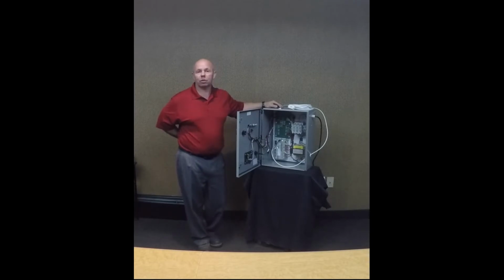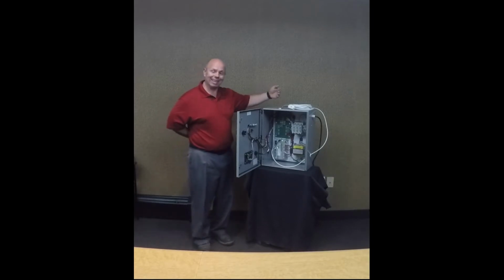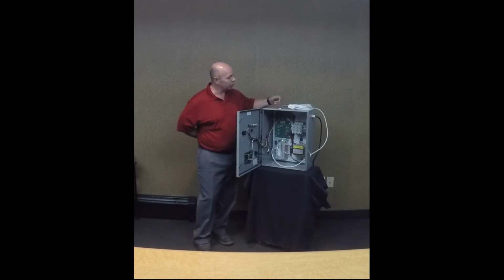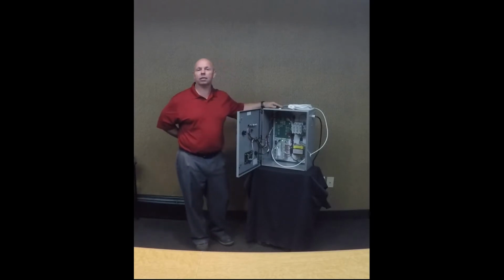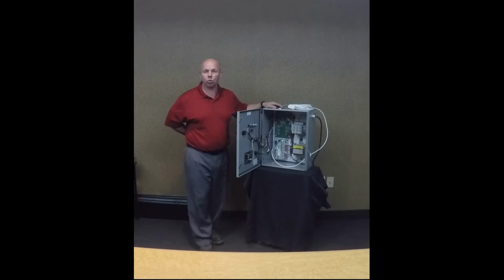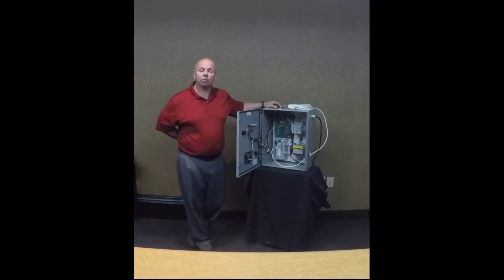There is also an option to have CTs provided with this so that you can have an AND function. You have light and current. But that signal is detected within 1 millisecond, goes back to the relay, and then we send a signal out to the shunt trip mechanism for a circuit breaker. The shunt trip voltage is 120 volts or 24 volts AC, depending on what is installed for your circuit breaker. I'd like to give you a quick example and show you how this works.